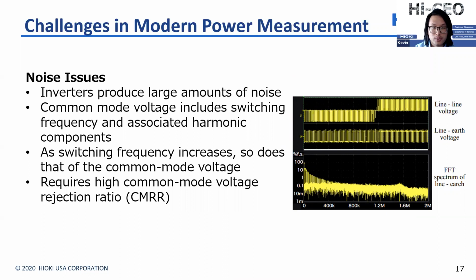So as we know too, with these new inverters, they produce a lot of noise. This will make it difficult for us to take good measurements. Since a power analyzer will measure your line voltage, a large common mode voltage is applied across all of the channels. This common mode voltage includes the switching frequency and the associated harmonic components. So the power analyzer needs to have a high common mode rejection ratio for the higher frequencies. Because as the switching frequency increases, so does your common mode voltage. And again, because the newer inverters are designed with increasingly high switching frequencies, it's really important we choose a power analyzer with high common mode voltage rejection.